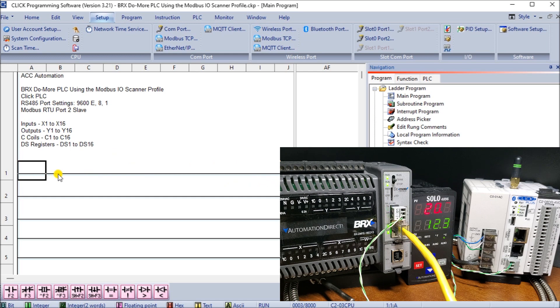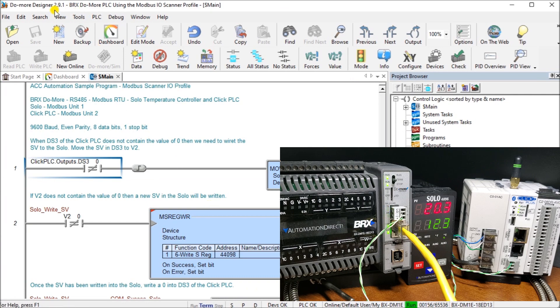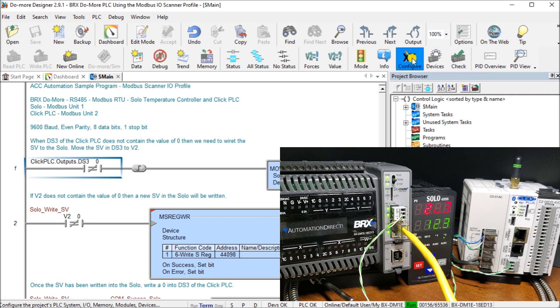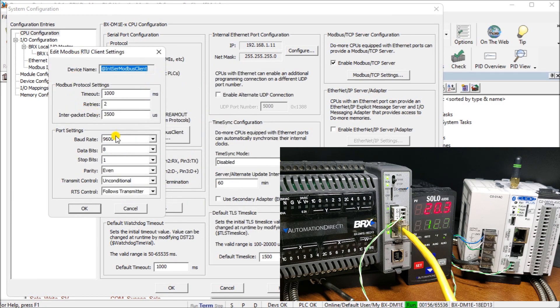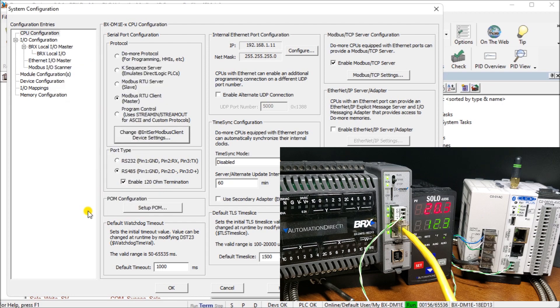So next what we'll do is take a look at our modbus I.O. scanner configuration. So going over to our DoMore designer version 2.9 or higher, currently right now I'm looking at version 2.91. We call up our system configuration by going under our project browser and under tools you'll see system configuration. We'll also see configuration up here or we can go PLC and then system configuration. All of these different options will get you to the same location. And last time we set up our serial port we have the RS-485 right here and our parameters were located right here in which we had the 9600 8.1 even. And that's how we set up the port which matches the same settings as our Click and our solo.